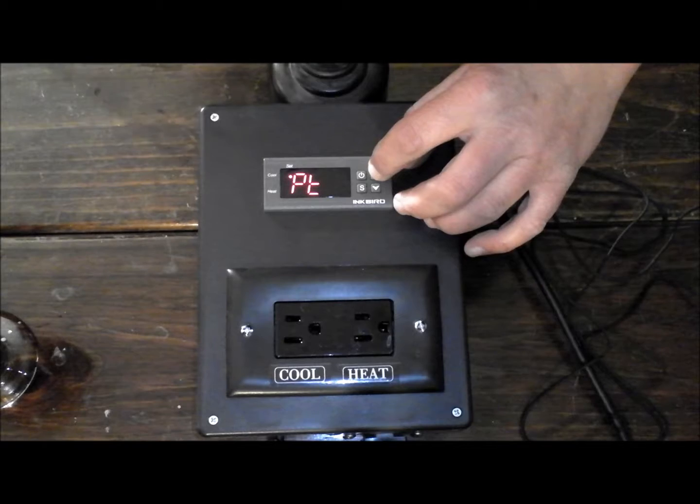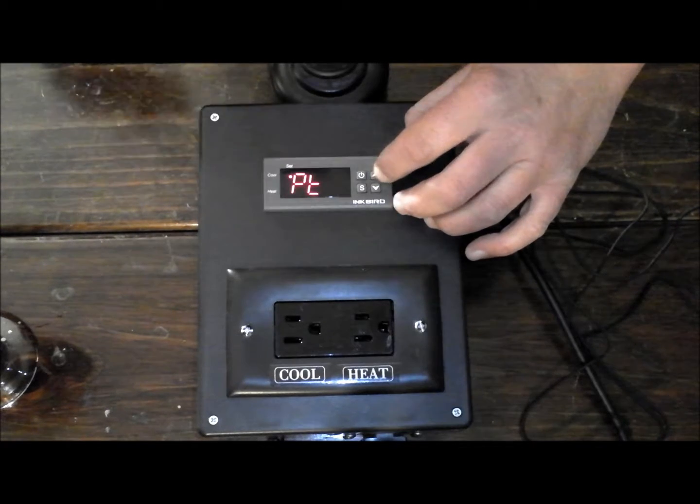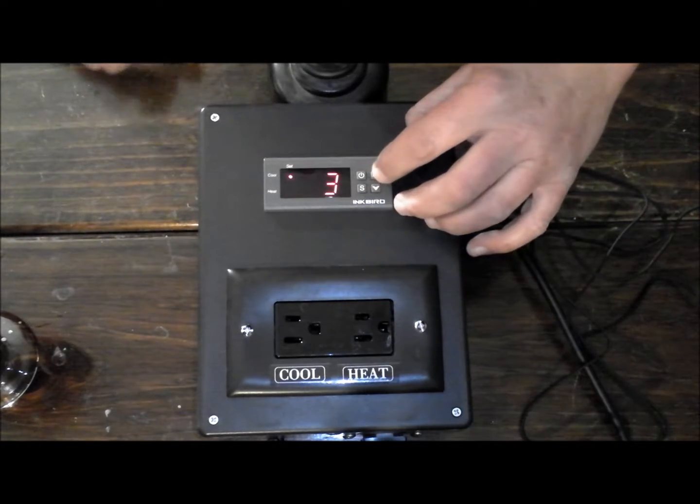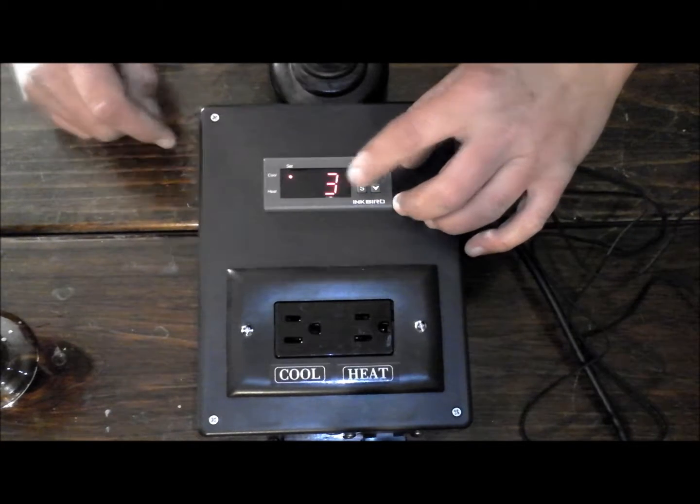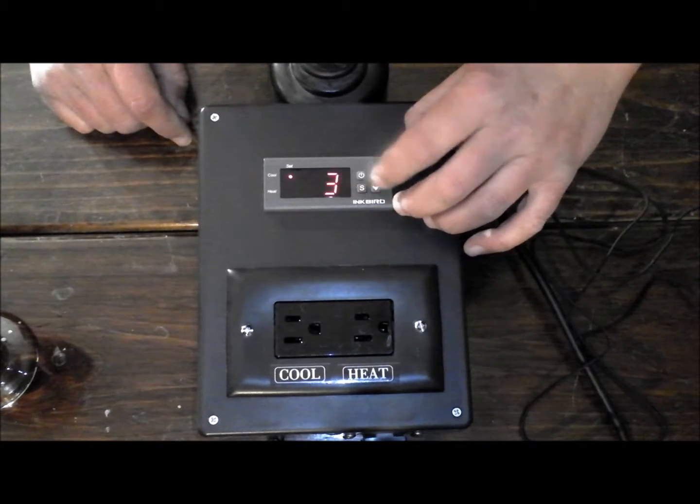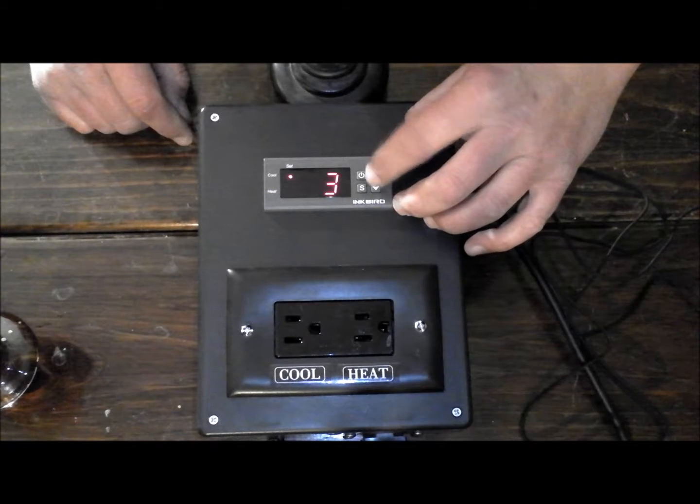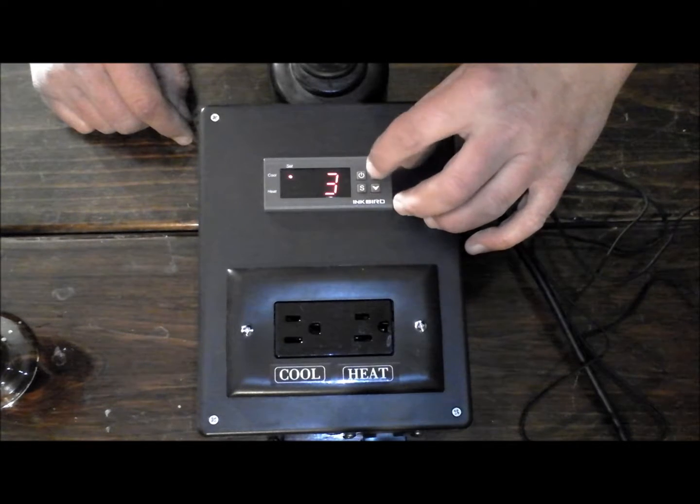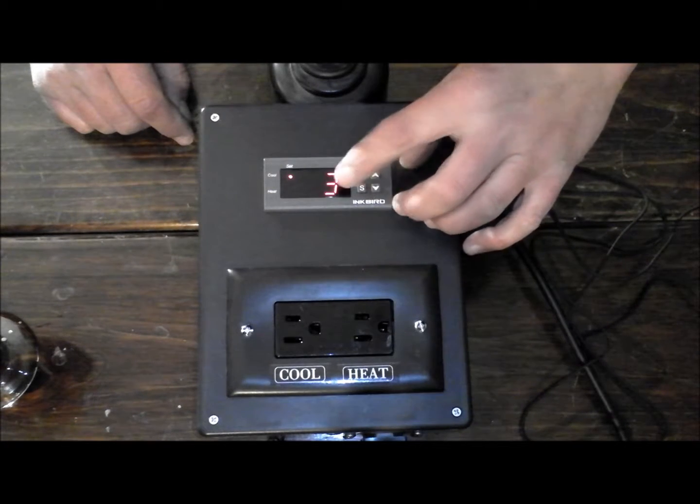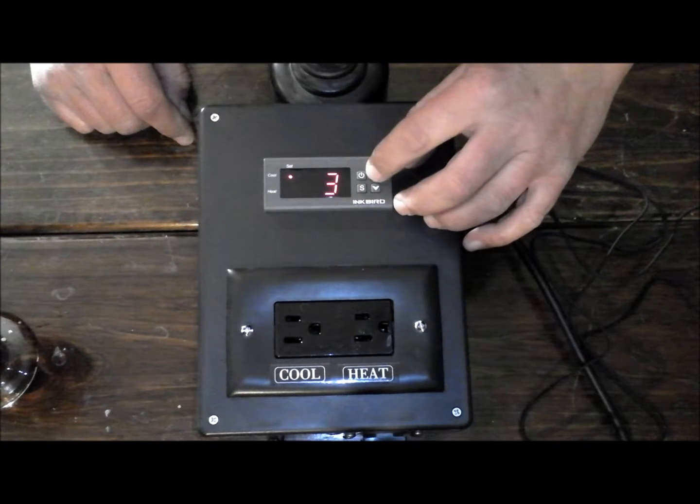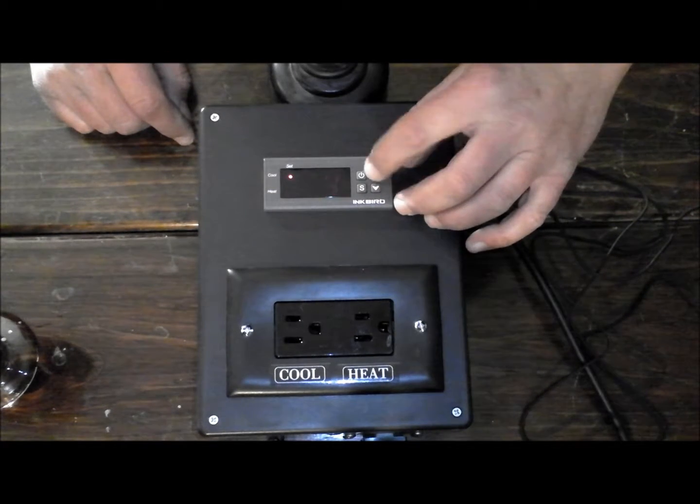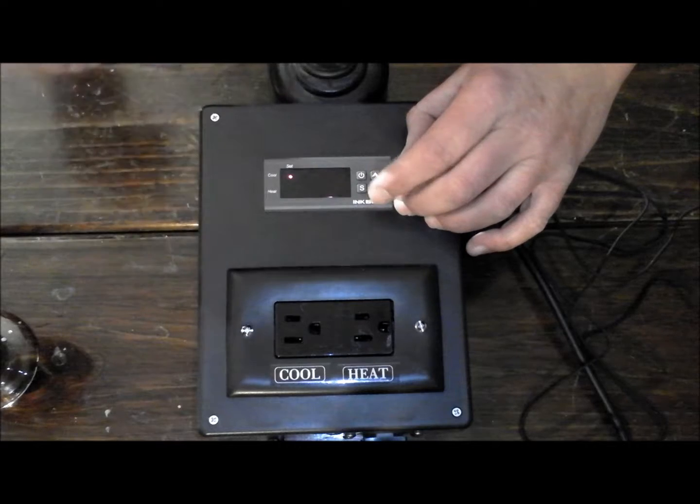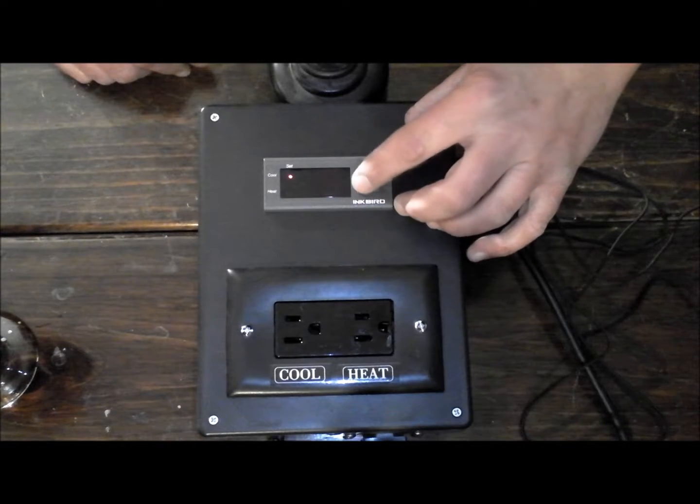The next one is PT, which is your compressor delay. This is done in minutes, so you can go from 0 to 10 minutes. Right now it's set at 3 minutes. I'd probably put it up around 5.